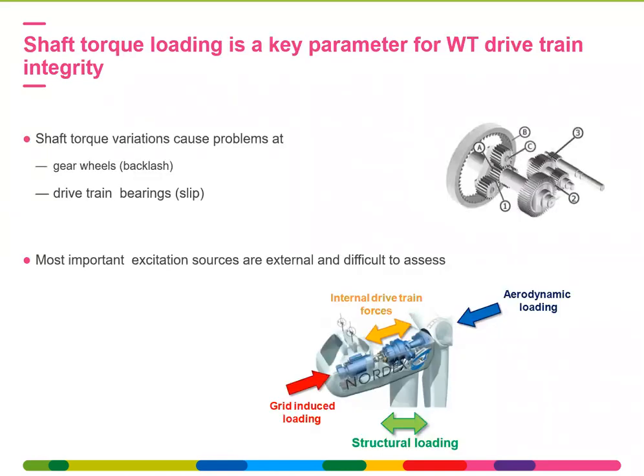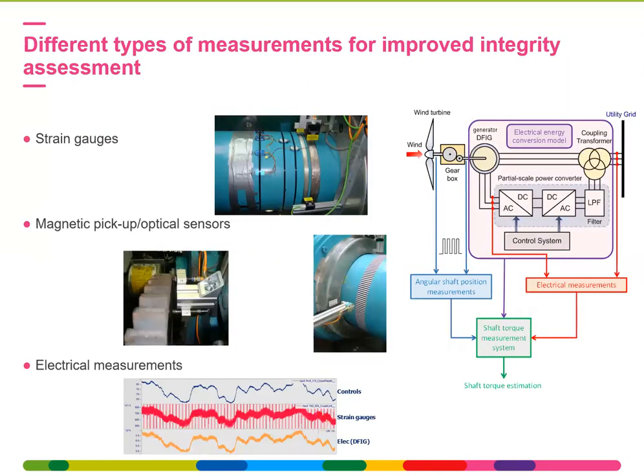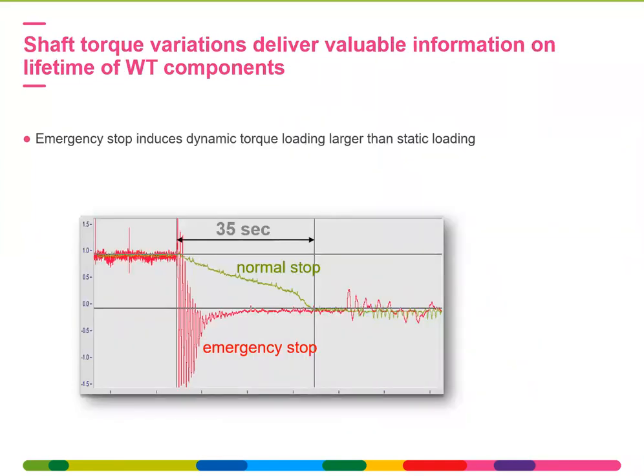There's another example on wind turbines, maybe of less importance for most of you, but this is an ongoing project in order to assess the criticality of a wind turbine shaft and to assess in more detail, electrically and mechanically, what the shaft line sees, and what damage could be done to the gearbox or the bearings of the wind turbine. So for instance, you can see that a normal stop has almost no dynamical content, while an emergency stop has a dynamic torque which is even higher than the static torque. This is still a research project, but the basic principles are similar to the classical power plants.